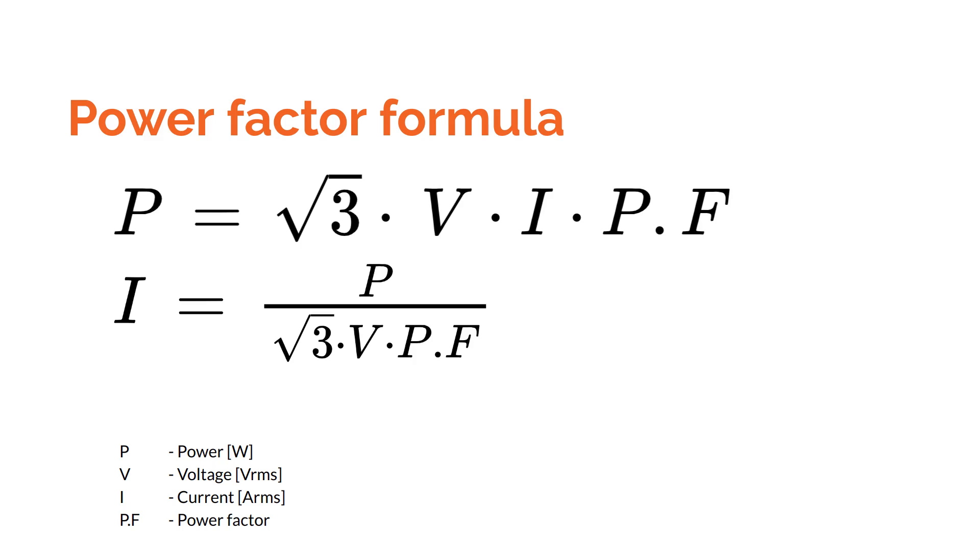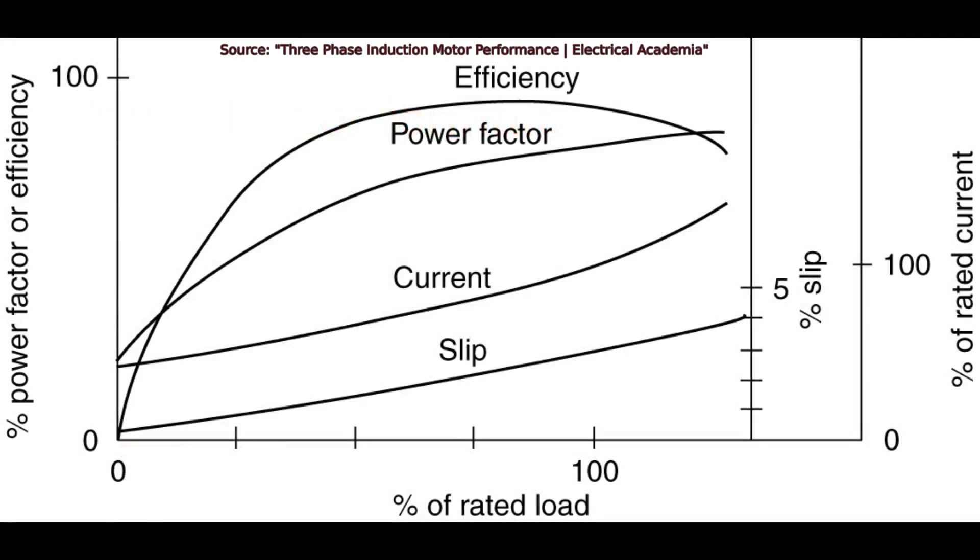This might seem a bit counterintuitive. So, here's a graph which gives an idea of how each parameter changes at different loads, after the motor has reached steady state, meaning no transients. We can see that the lower the load, the lower the current, despite having a lower power factor.